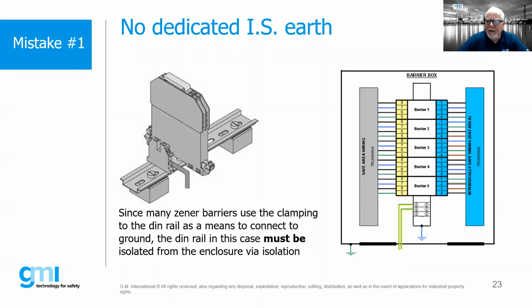The slide on the right-hand side shows our intrinsically safe wiring. On the left-hand side, we see our safe wiring, and then the incoming and outgoing, and that's typically what you would find. Notice that our intrinsically safe wiring coming out is our clean earth. And then down at the bottom left-hand side, that's our dirty earth that we're going to be grounding the enclosure to. So that's the normal earth that we would find within our facility.